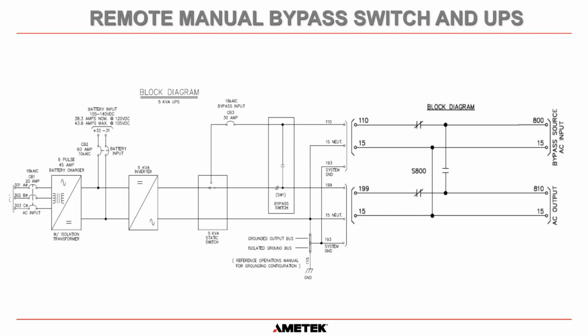If we are in the bypass isolated position, so this is open, power is flowing down here and out there. Terminals 110 and 15 have no power. Terminals 199 and 15 have no power. We're going to go in and disconnect the battery, so there's no power. We are going to disconnect the AC input. There is no power.